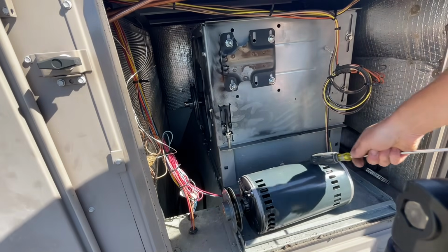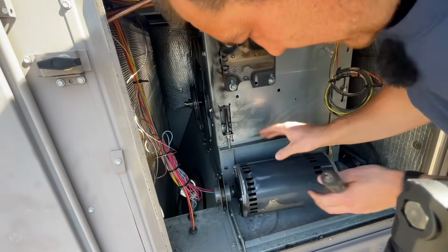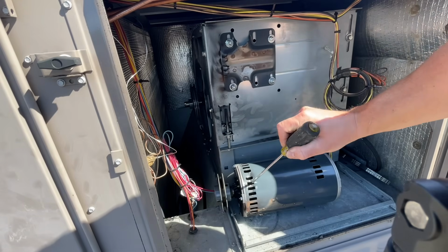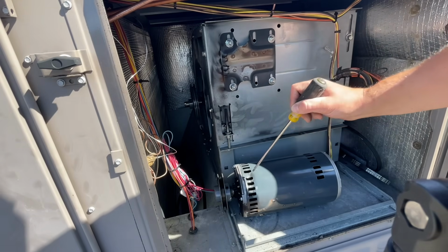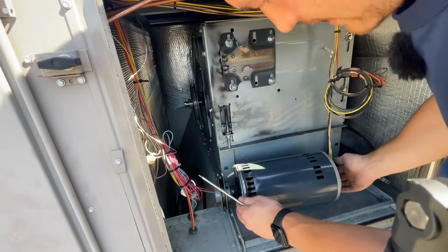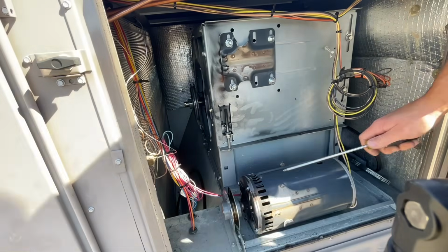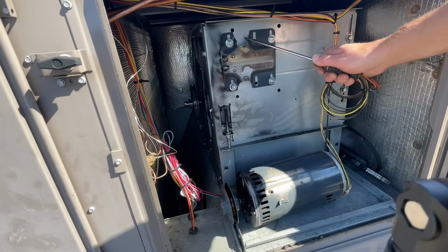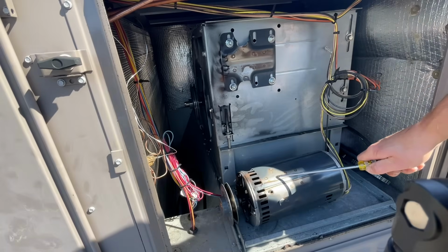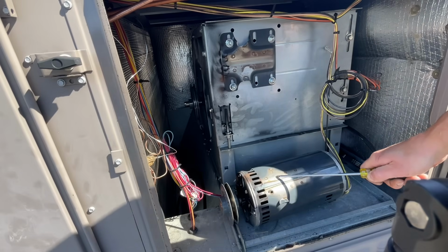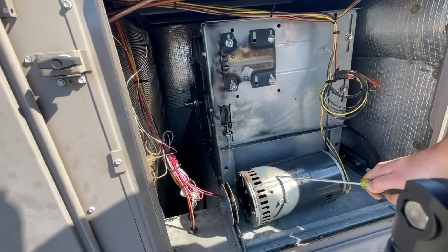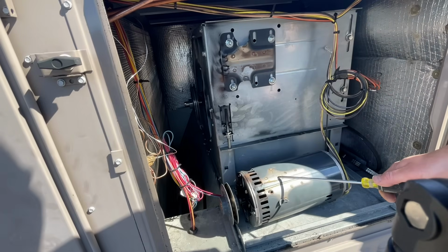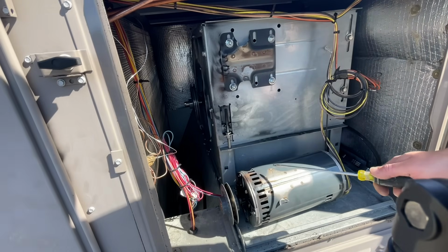There we go. This here has taken a major hit. The cooling fan inside the motor almost was grinding up against that housing plate, but it's just free. And here is where, once upon a time, that welded bracket was holding this motor in place. That is insane. I've seen rooftops with belt tensions that are just ridiculously over tightened, and I've never seen this in my life. I have no idea how this happened.